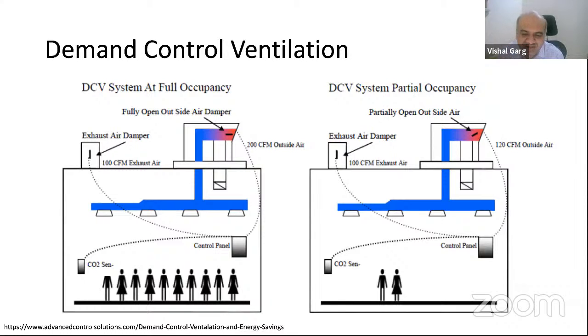So here you see a CO2 sensor put into the space, and when there are more people, more air is brought in, and when there are fewer people, less air is brought in. What's the benefit of bringing less air? When we bring less outside air, we need less cooling, because the outside air is hot and has to be cooled, so we save on the air conditioning load by reducing the fresh air pulled in. This is a simple technique useful for places with highly variable occupancy. If occupancy is fixed, it doesn't help, because we'd provide the same amount of fresh air all the time.